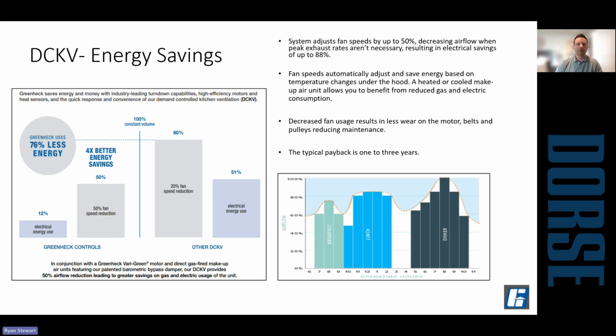As far as savings are concerned, a 50% reduction in airflow is an 88% reduction in the cost to operate the electric motor. Where the biggest savings is actually in the makeup air, though. When you're at a reduced exhaust, that's also the supply, so it's less air that you have to heat and cool. So that's where you see some of the biggest savings. Through PSE, there's some programs around here for retrofits. So if you have restaurants that are interested in control upgrades, in some cases, the rebates can pay for the full cost of the control panel.